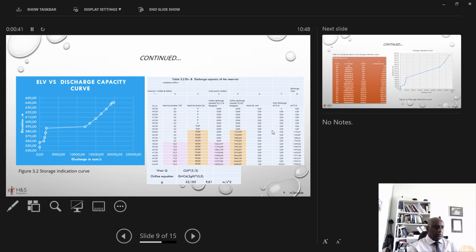This is 18 meters for the two turbines in the beginning. It means the minimum operating level is 560 for the lower penstocks. The elevation of the penstock is 542 at the center of the penstock, actually. Then the difference is 18 meters, because that is the minimum pool level to commence working.